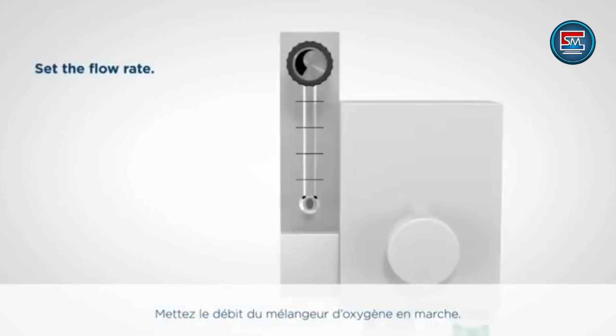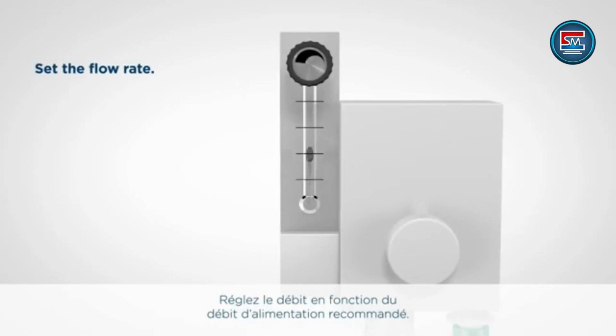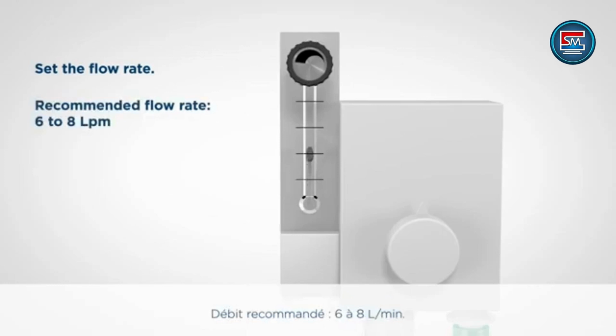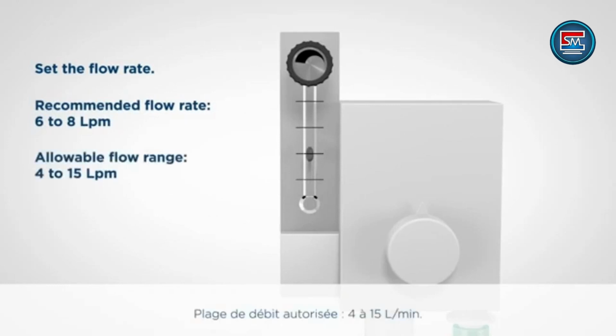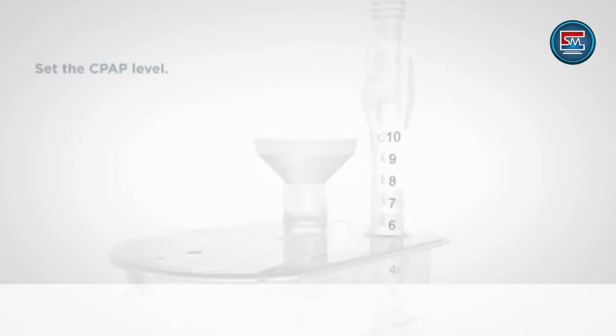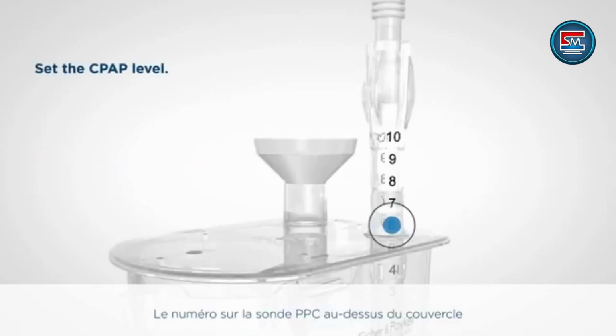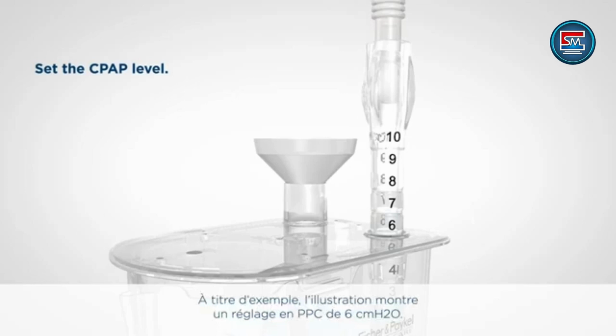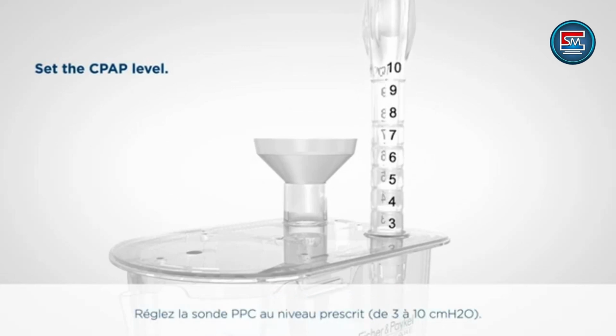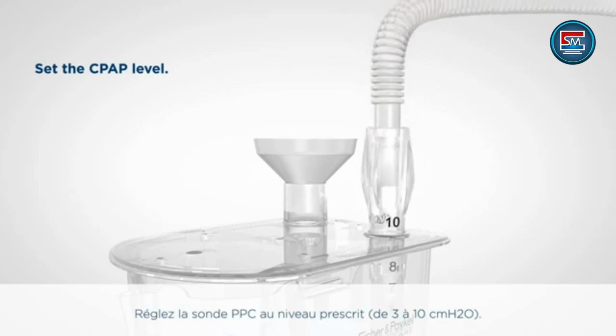Remove the correct port cap from the pressure manifold before connecting any monitoring device. Turn on the flow from the oxygen blender. Adjust the flow rate to the prescribed input flow rate. Recommended flow rate 6 to 8 litres per minute. Allowable flow range 4 to 15 litres per minute. The number on the CPAP probe above the lid indicates the CPAP pressure in centimetres of water. As an example, the illustration shows CPAP setting of 6 centimetres of water. Set the CPAP probe at the prescribed level 3 to 10 centimetres of water.